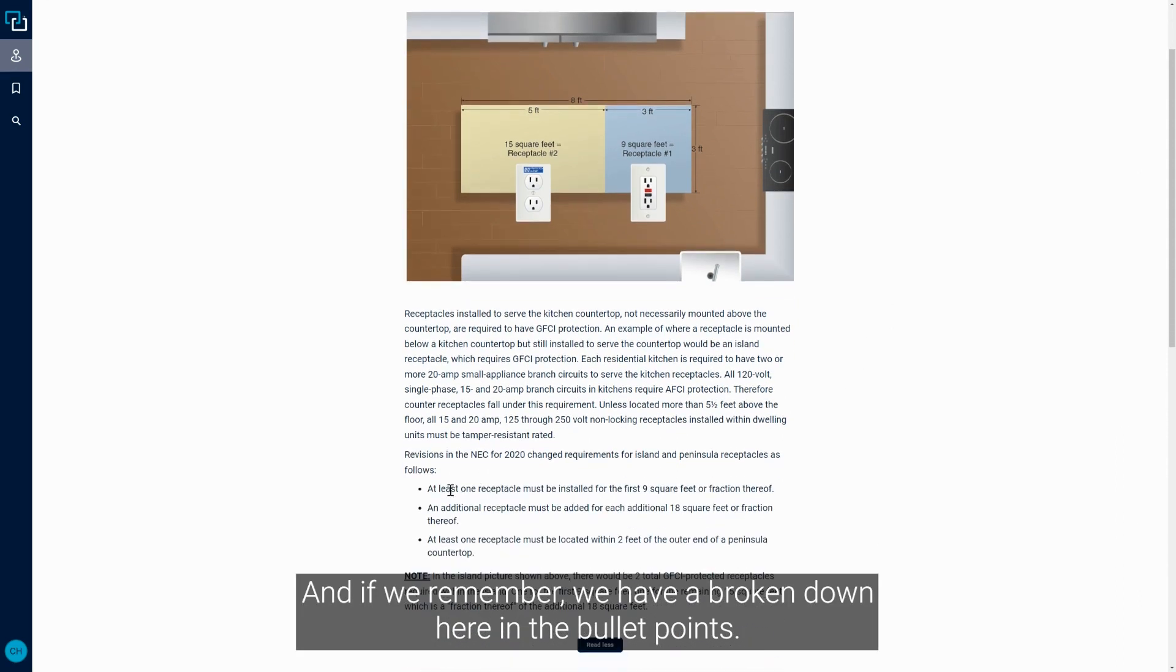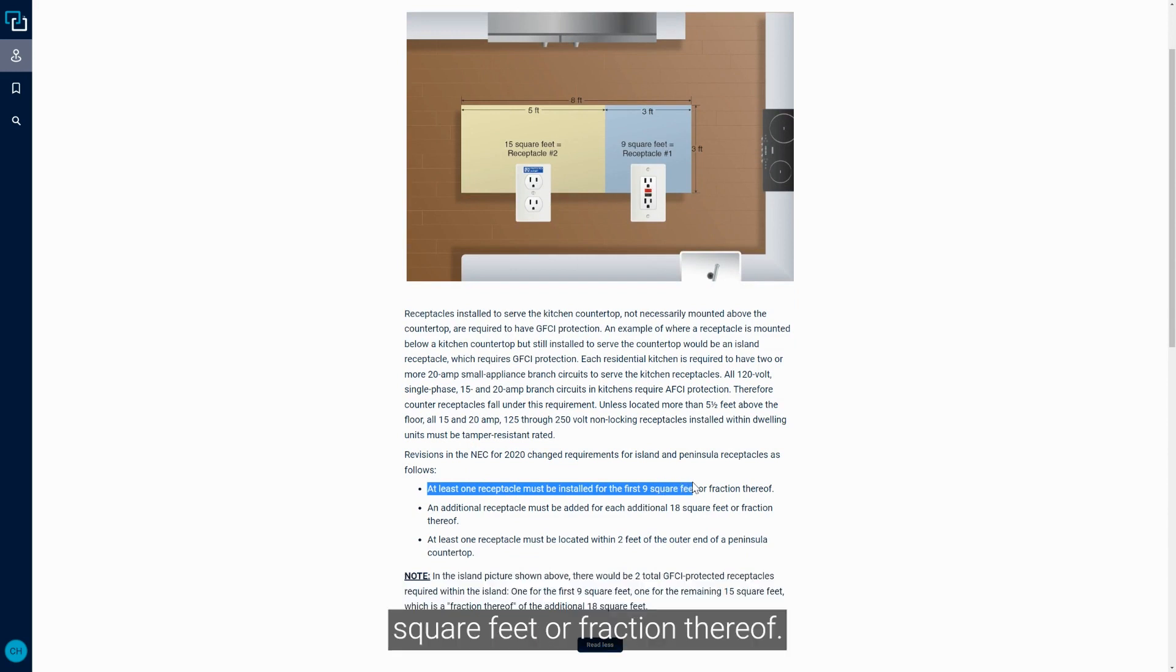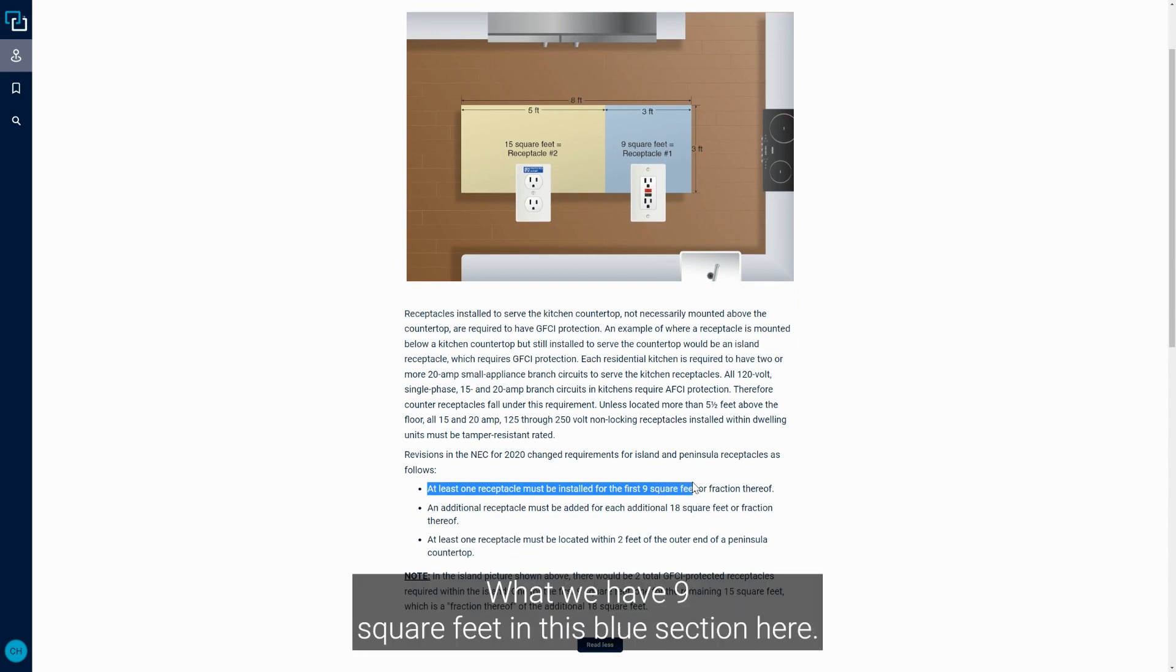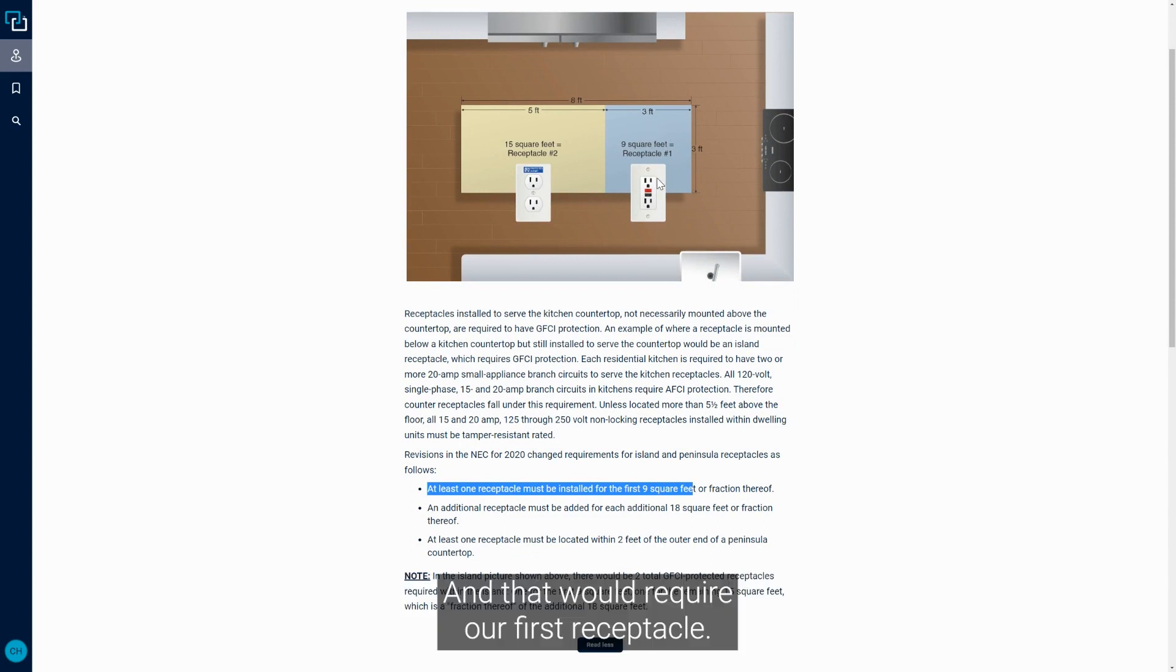And if we remember, we have it broken down here in the bullet points: at least one receptacle must be installed for the first nine square feet or fraction thereof. Well, we have nine square feet in this blue section here, and that would require our first receptacle.